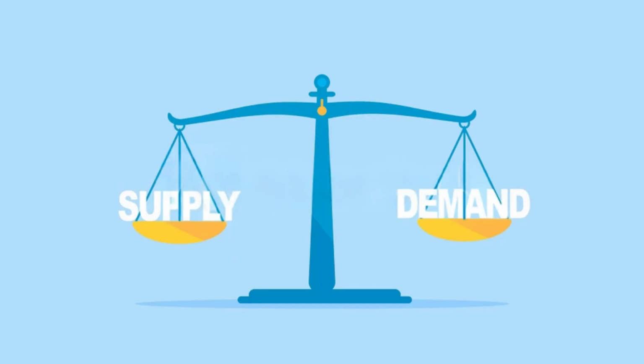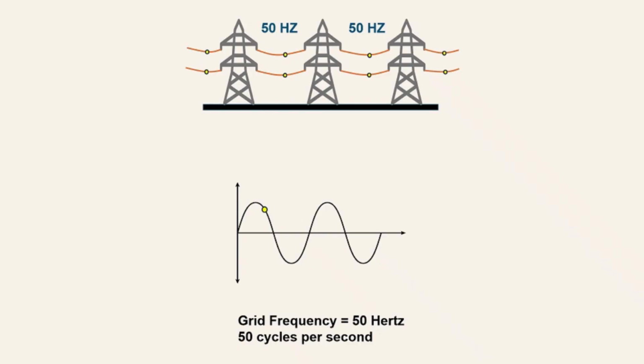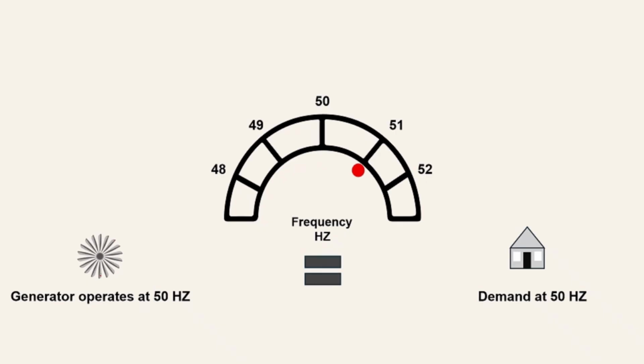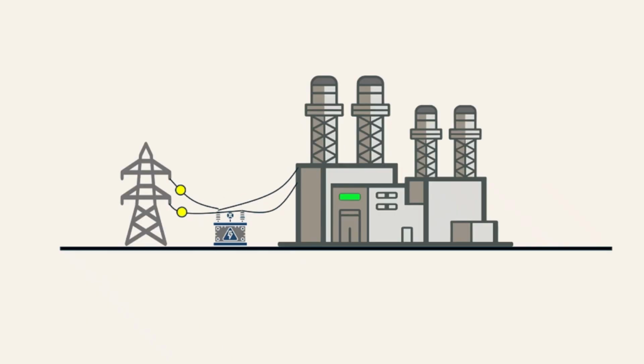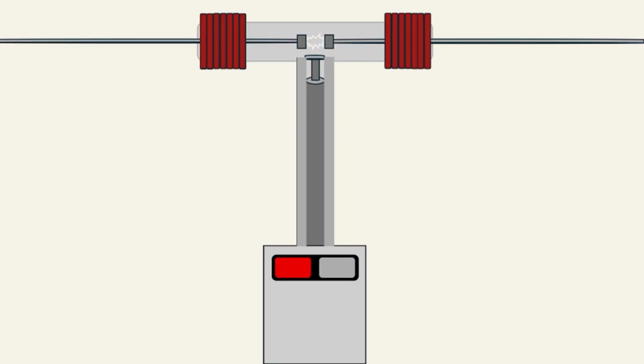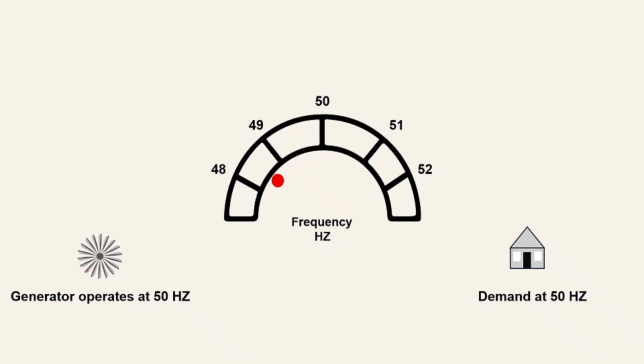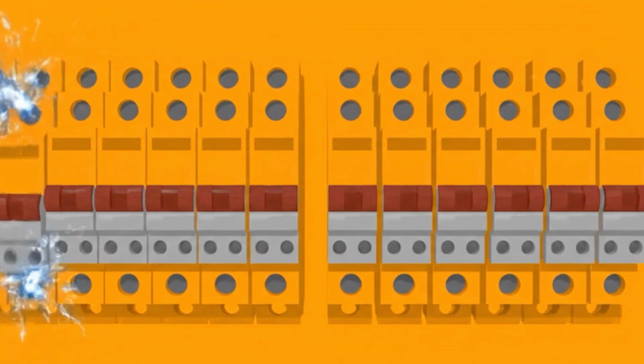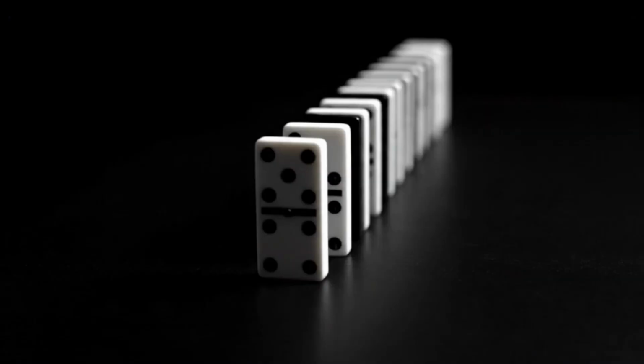To understand why collapses happen, we need to understand balance. The grid operates at 50 Hz, a measure of how synchronized generators are with power demands. When supply matches demand, the system runs at exactly 50 Hz. But when something disrupts this, a plant trips offline, a transmission line fails, the frequency shifts. If it drops too low or rises too high, protective systems automatically shut everything down to prevent equipment damage.